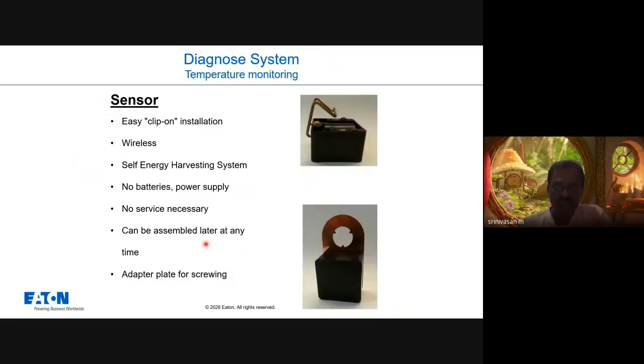To overcome this, we have a system called the diagnosis system. It's basically a wireless sensor system. It can be installed anywhere on the bus bar. It can be clipped on, and it works on the principle of self energy harvesting. There are some other manufacturers who have an equivalent similar system, but the point is they need an auxiliary power supply for operation of the sensor. They also need batteries, and you need to replace the battery after some time. If you want to replace the battery, then you have to do a shutdown for safety reasons. All these things are eliminated by this wireless thermal sensor system.